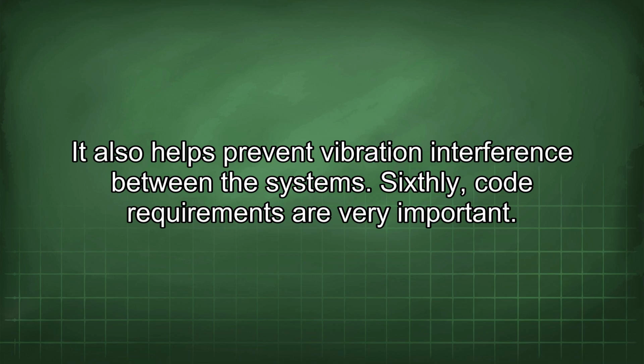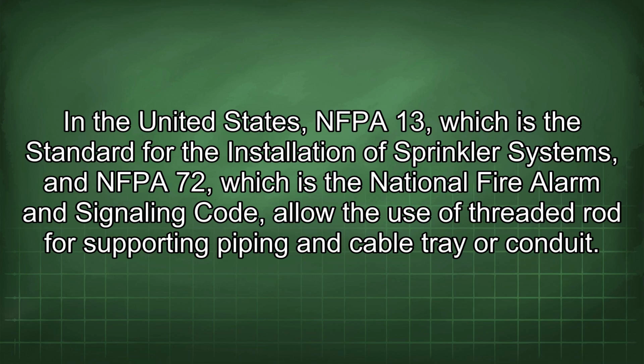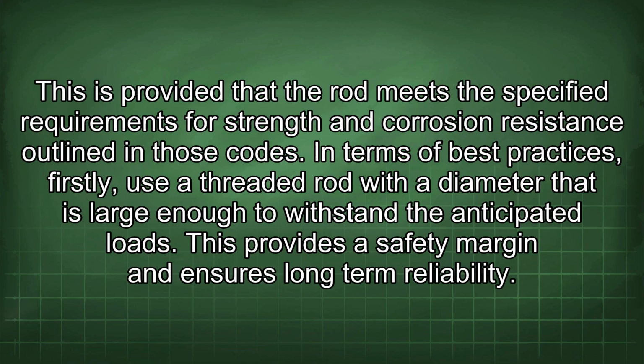Sixthly, code requirements are very important. In the United States, NFPA 13, which is the standard for the installation of sprinkler systems, and NFPA 72, which is the National Fire Alarm and Signaling Code, allow the use of threaded rod for supporting piping and cable tray or conduit. This is provided that the rod meets the specified requirements for strength and corrosion resistance outlined in those codes. In terms of best practices, firstly, use a threaded rod with a diameter that is large enough to withstand the anticipated loads. This provides a safety margin and ensures long-term reliability.